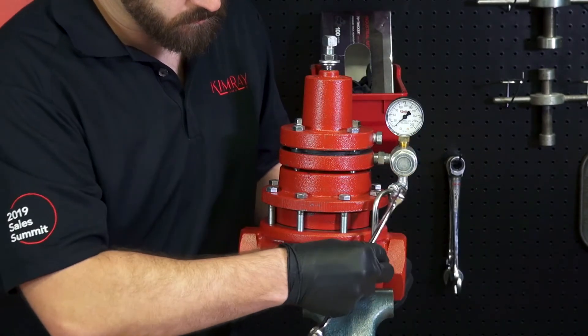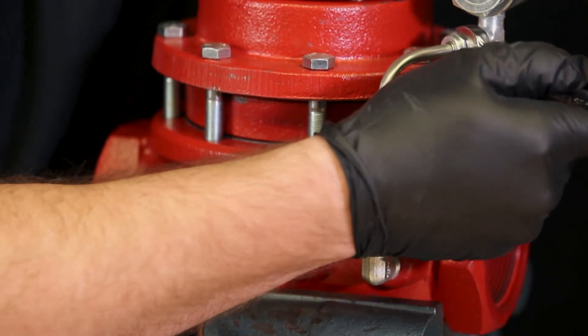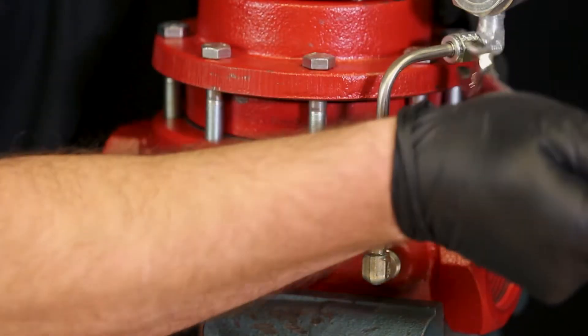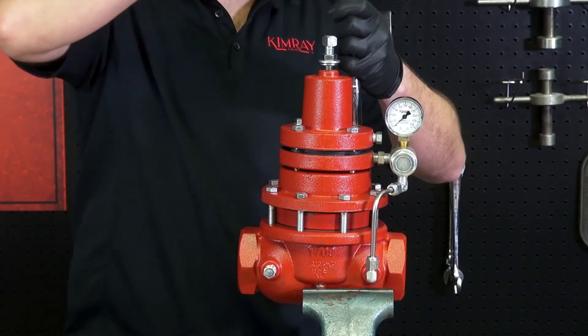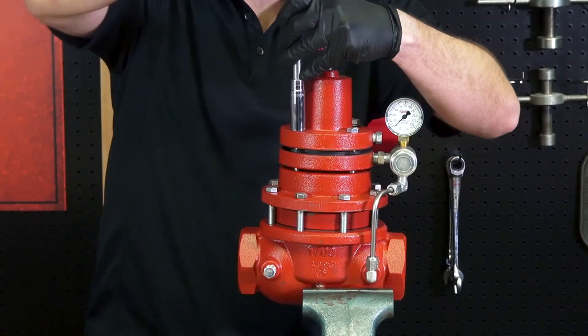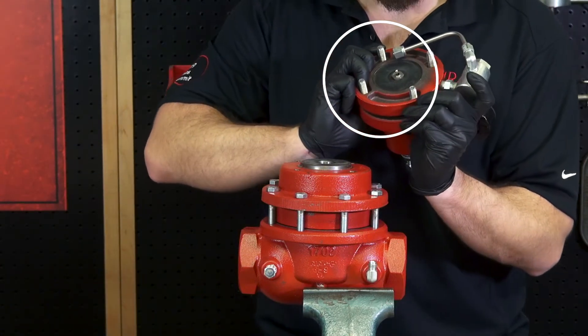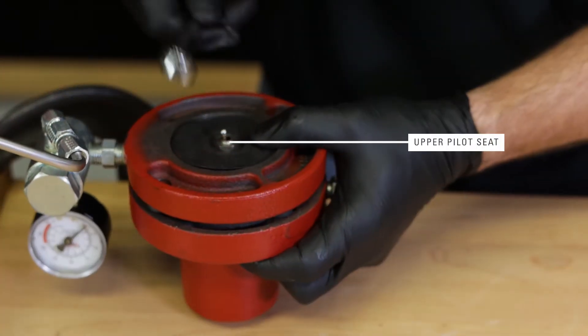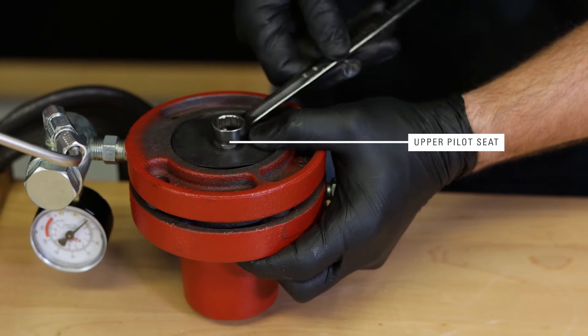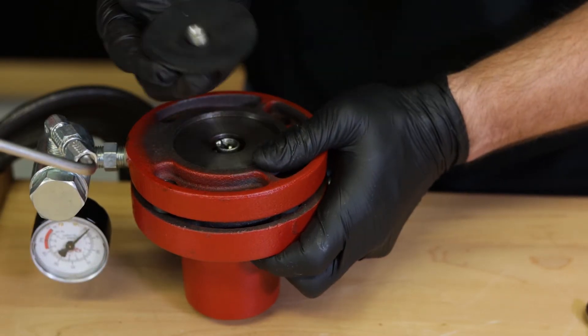Then, loosen the tubing. Remove the bonnet bolts but leave them in place to keep the assembly from coming apart. Remove the bonnet from the body and inspect the diaphragm for damage. If it's damaged, it will need to be replaced. Remove the upper pilot seat with a 9/16ths wrench. Keep the upper seat assembly together as you separate it from the upper diaphragm plate.